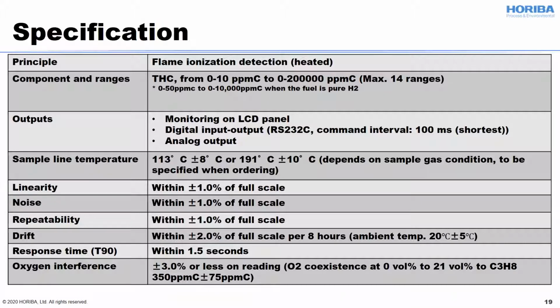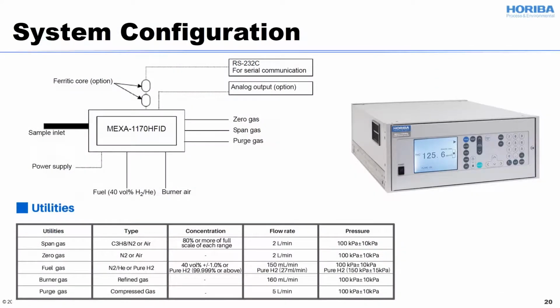RS-232C digital in and out and analog output are available. The sample heated block is maintained at 113 degrees C or 191 degrees C, depending on the application and the target hydrocarbons. This is a system configuration. I just want to touch on the utilities we use. Span calibration is done by propane and the zero is by nitrogen. As you can see, fuel gas has options of hydrogen-helium base or pure hydrogen.